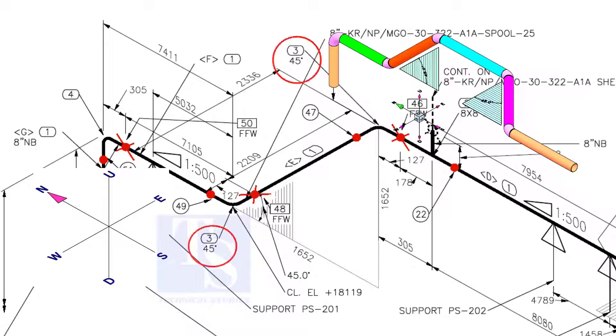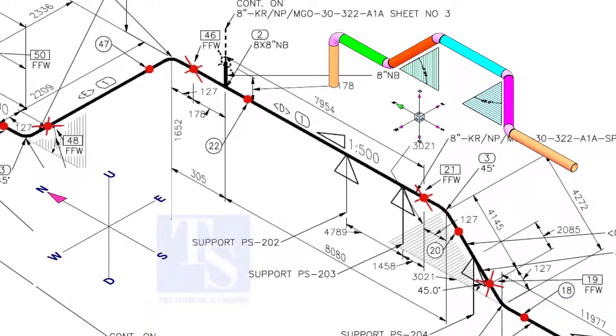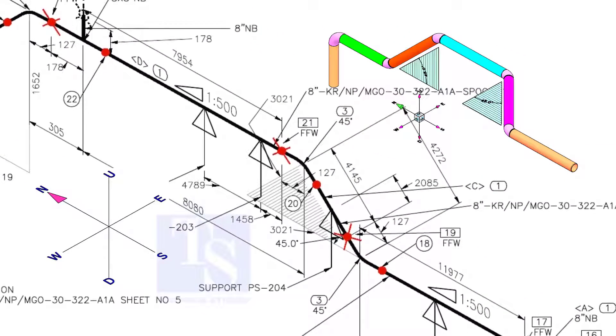Check the rolling degree — both these elbows are 45-degree. Triangle 1 is to 500 means the pipe is sloping towards the north by 1 millimeter in every 500 millimeters of length.